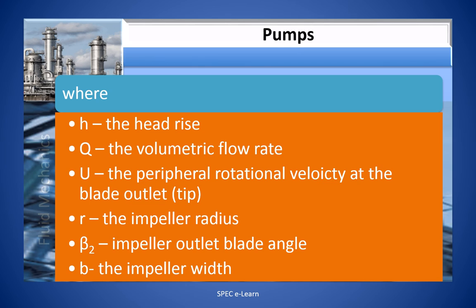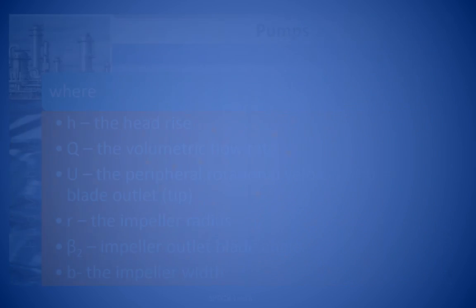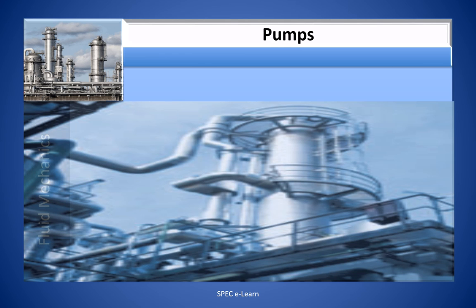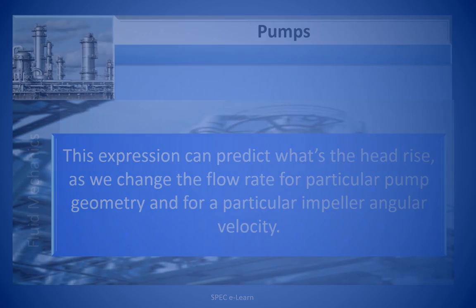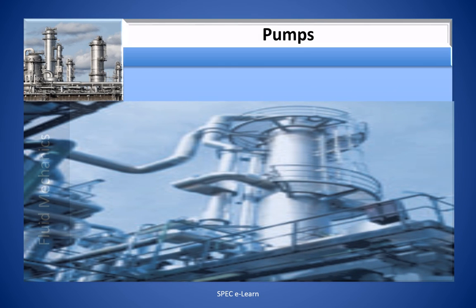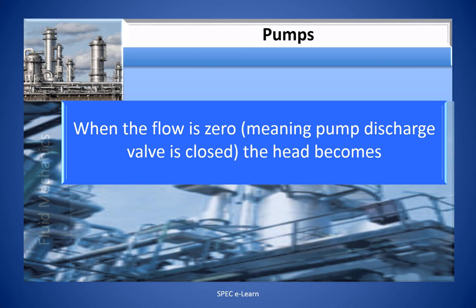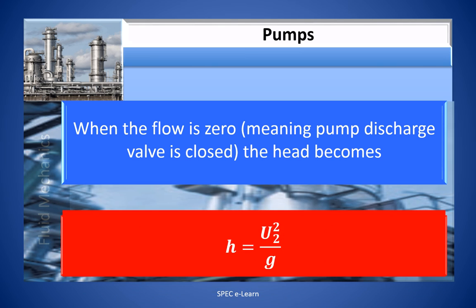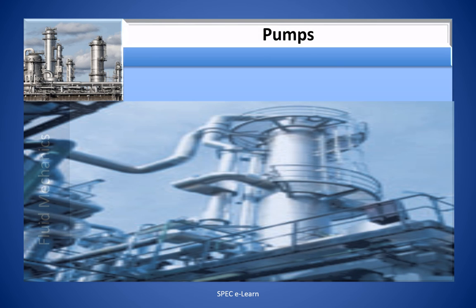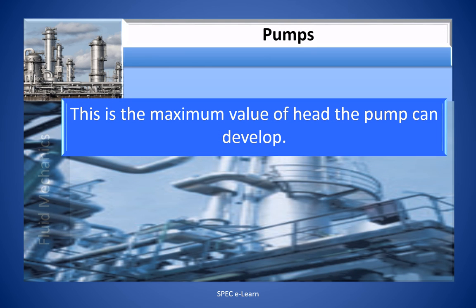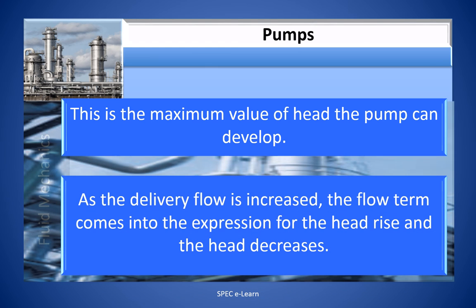This expression can predict the head rise as we change the flow rate for a particular pump geometry and a particular impeller angular velocity. When the flow is zero — meaning the pump discharge valve is closed — the head becomes H = U2² / g. This is the maximum value of head the pump can develop. As the delivery flow is increased, the flow term comes into the expression for head rise and the head decreases.